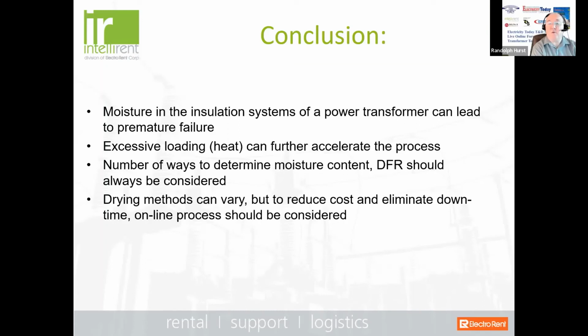Okay, thanks. Next question. What is the percentage of installed transformers in the United States that have been identified as having a moisture issue based on annual liquid sampling results? Well, that's a good question, and I don't have the answer right offhand. But I can tell you this. First of all, I would say that the percentage of transformers with a moisture condition is probably more unknown than it is known. So even the best statistics to tell you that there's a moisture issue may not be entirely accurate.